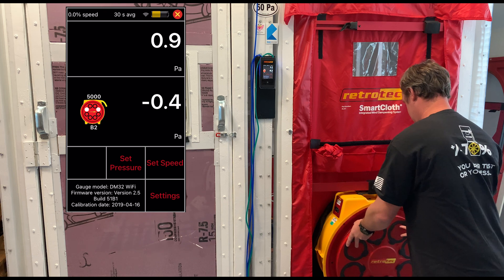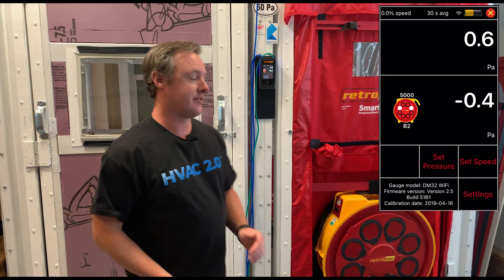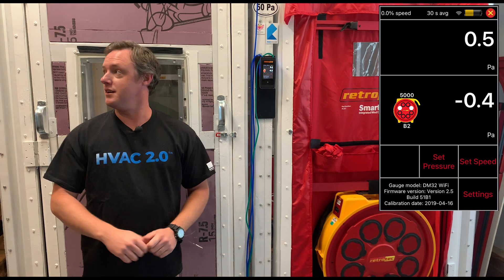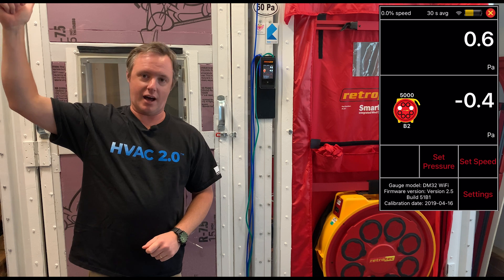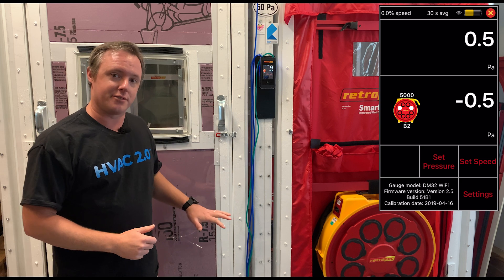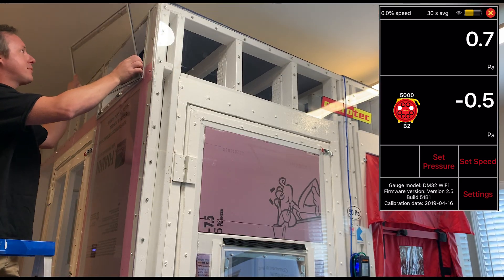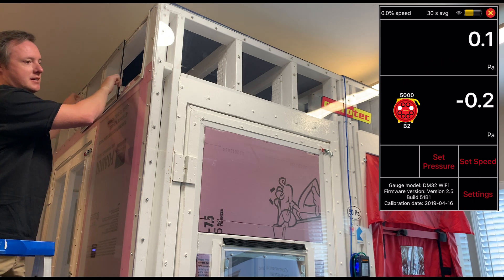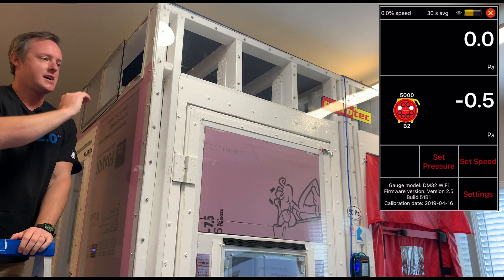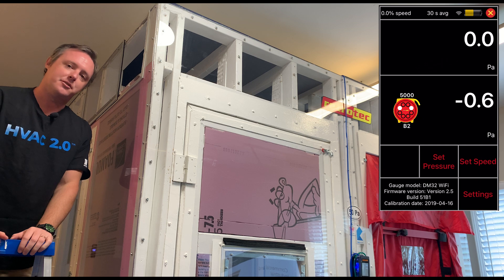If I put that back, it will stabilize back to where it was. And of course if I do the opposite — if I remove a panel from the top and create leakage at the top of the building — it's going to drive that pressure down to the bottom. Here I'll remove this side panel off the top to add some leakage. Now we can see channel A go to zero and that pressure getting pushed down to the bottom where we're picking up that negative pressure on channel B.